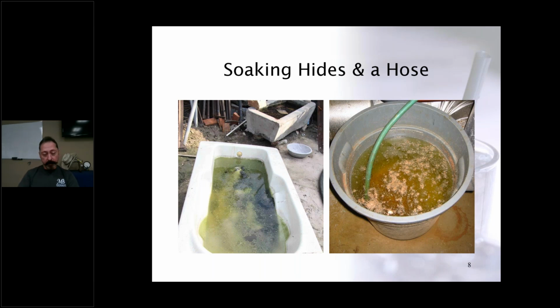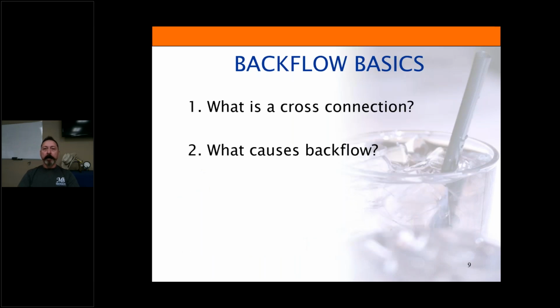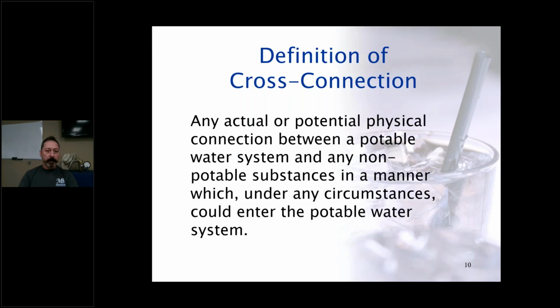And every time they flushed that hydrant, it would also repeat the same conditions. So it's understanding what a cross connection is and how backflow incidents occur, as far as the hydrology and that sort of thing, how all this happens. By definition, a cross connection is any actual or potential physical connection between the drinking water system and any source of contaminant, in such a way that contaminants can enter the drinking water or the potable system through the cross connection that you've made.